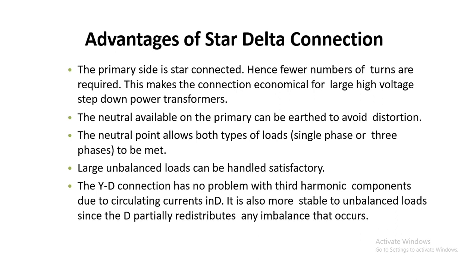The star to delta connection has no problem with third harmonic components due to circulating currents in the delta. It is also more stable to unbalanced loads since the delta partially redistributes any imbalance that occurs.